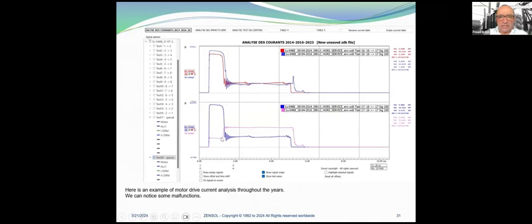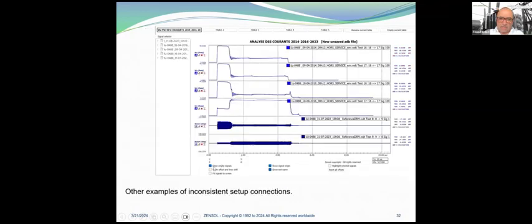Here it's two problems of bad connections. Here is another example of inconsistent setup connections. Throughout the years, one measurement was in 2014, which you can see on the top here, 2016 in the middle, and 2023 the last one. So you can see that the motor current connection was not consistent.